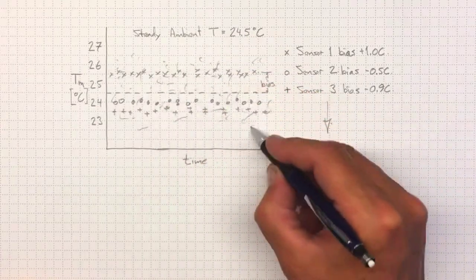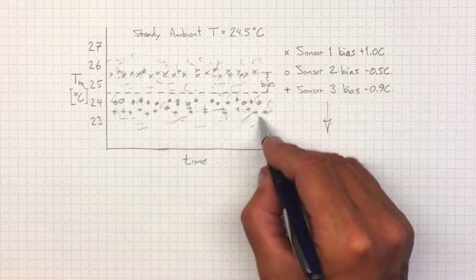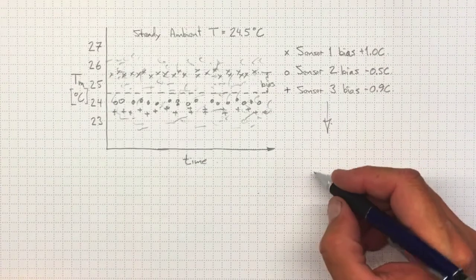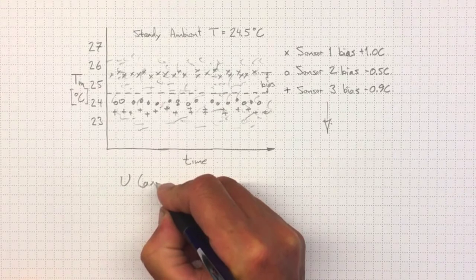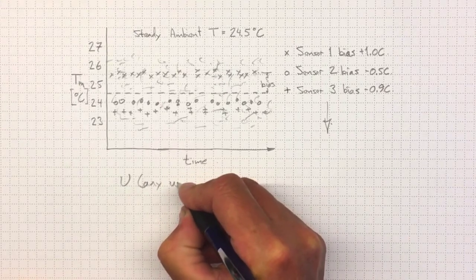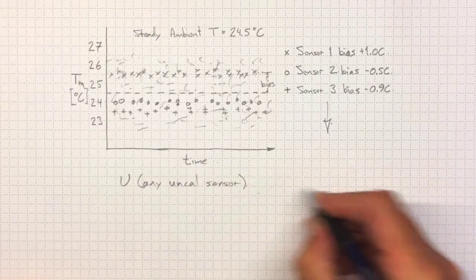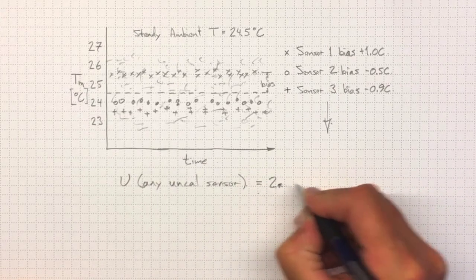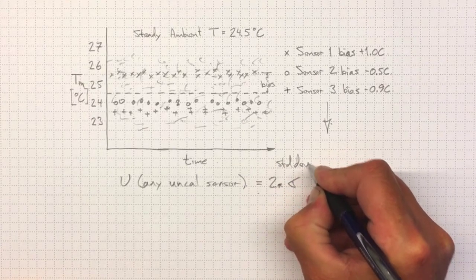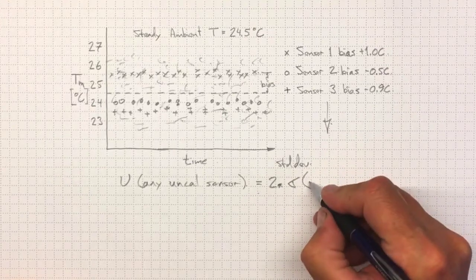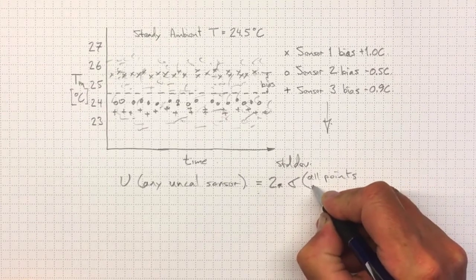And if I wanted to estimate the uncertainty that I'd get by just picking a random sensor, then that uncertainty for any uncalibrated sensor would wind up being equal to two times the standard deviation of all points from many sensors.